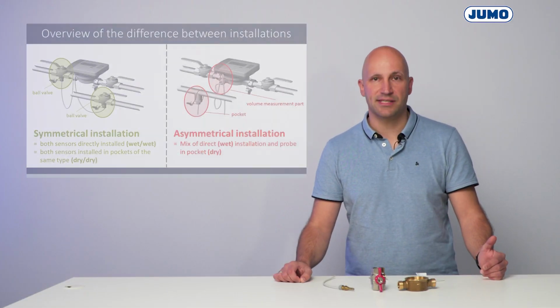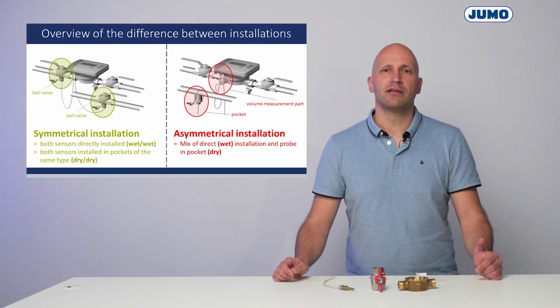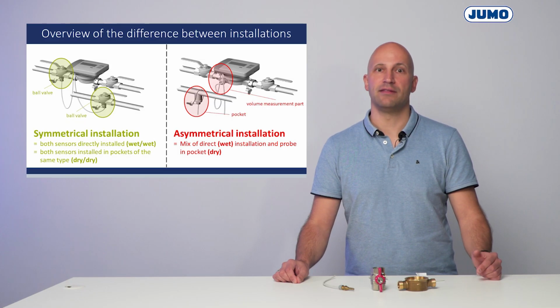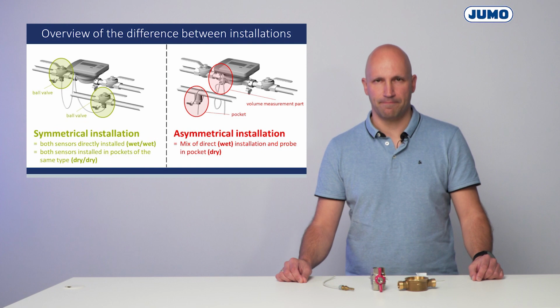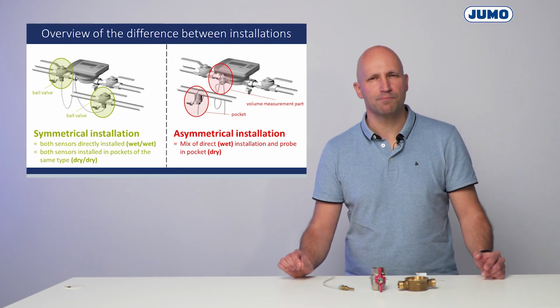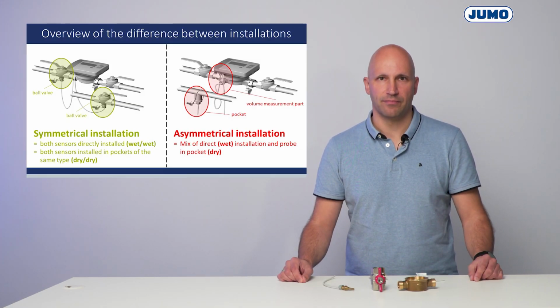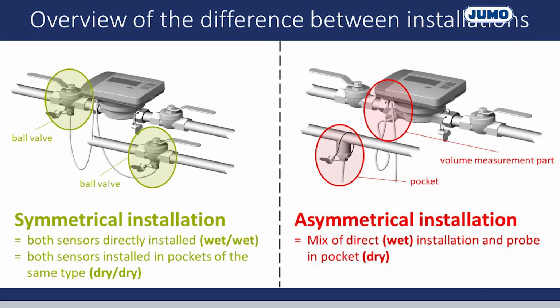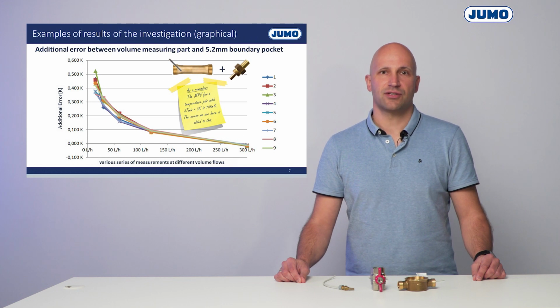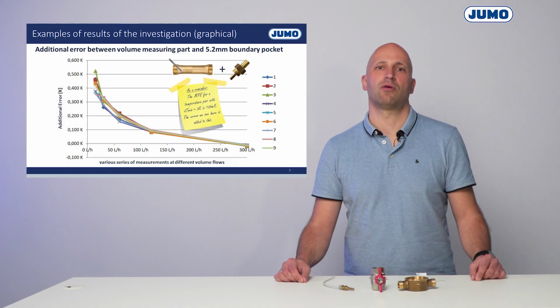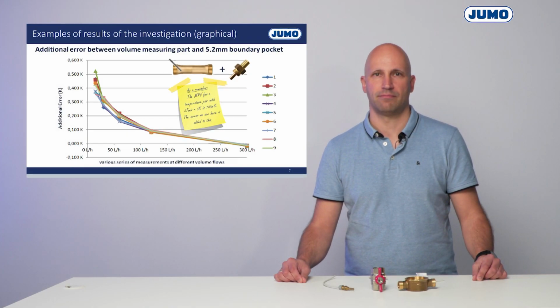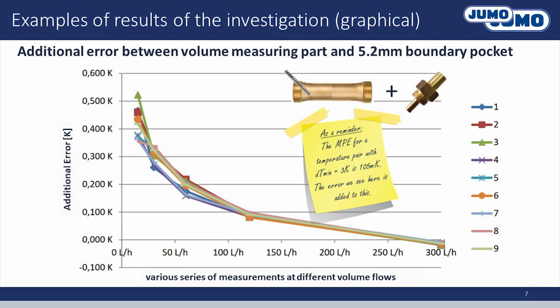Let's now move to another important point: the difference between symmetrical and asymmetrical installation of temperature probes. In symmetrical installations, both probes are mounted in the same way, either both directly in the medium or both in pockets. This symmetrical arrangement ensures that both probes measure the temperature under almost the same conditions, an important condition for accurate measured values. Asymmetrical installation, on the other hand, means that one probe is installed directly in the medium, while the other is in a pocket. This difference in the installation causes an additional error. The different heat conduction error of the installation points causes an additional error when measuring the temperature difference between flow and return. The lower the flow velocity of the medium, the higher the error.